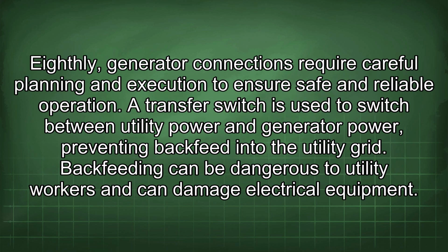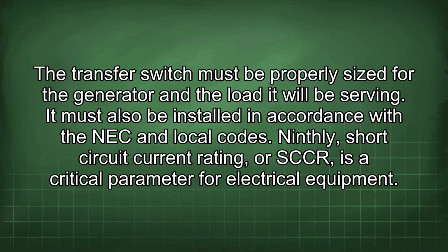Eighthly, generator connections require careful planning and execution to ensure safe and reliable operation. A transfer switch is used to switch between utility power and generator power, preventing backfeed into the utility grid. Backfeeding can be dangerous to utility workers and can damage electrical equipment. The transfer switch must be properly sized for the generator and the load it will be serving. It must also be installed in accordance with the NEC and local codes.